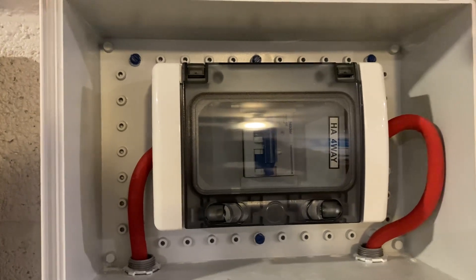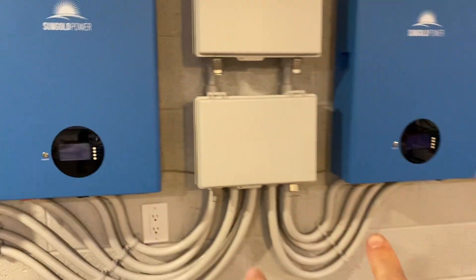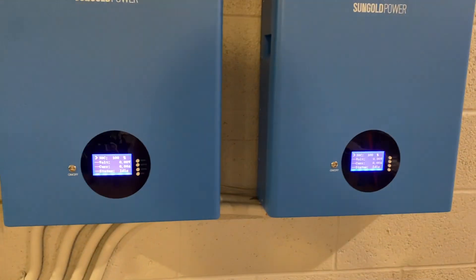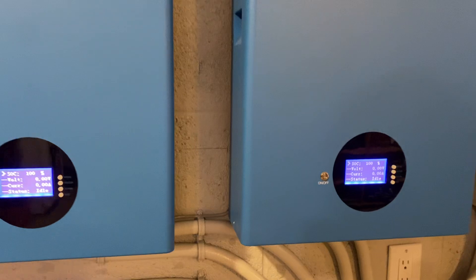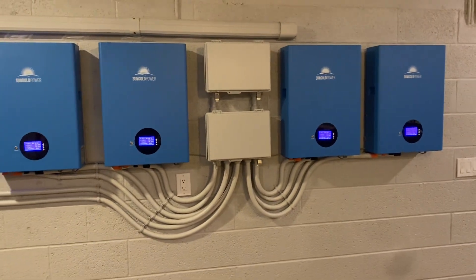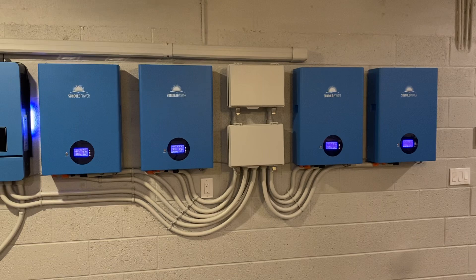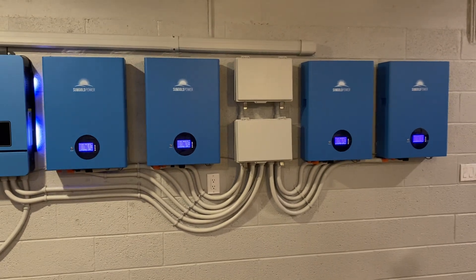The main hot line off the positive goes through a breaker - I got it through Signature Solar, rated I think maybe 200 amp - and then it feeds the inverter. Since I sent all the batteries over to that bus bar, I'm now charging and discharging much more evenly. These two new batteries show seven amps coming out; the two older batteries are discharging a little more at nine amps. The bus bar is definitely evening them out a lot quicker than just cabling them together with the built-in plugs.